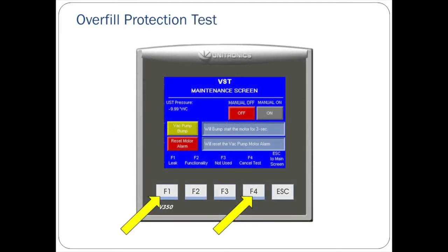Overfill Protection Test. It is the responsibility of the startup contractor to test the overfill protection once the programming is complete. An important shortcut while testing is, once the Green Machine is in an overfill alarm, navigate to the maintenance screen, then press the F1 and F4 buttons at the same time. A screen will pop up prompting for confirmation of manual override of the overfill alarm. Push confirm to avoid waiting the full 2 hours for the alarm to clear naturally.